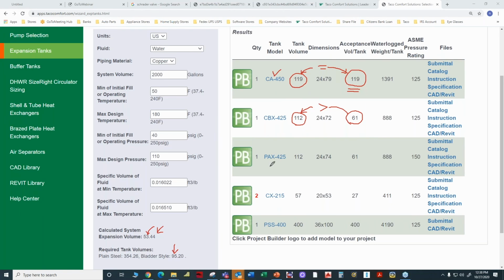Now I'm going to skip over the PAX for a moment and go to the fourth one down, which is the CX. And if you'll notice, the steel container tank is 57 gallons. Well, that's not enough. But over here we have the number 2. So if we multiply 57 times 2, that's going to be 114. And 114 is greater than 95, so it meets that criteria. We have to multiply the 27 times 2, that's 54. And 54 is greater than what's required by the expansion, and so that tank will do the job.